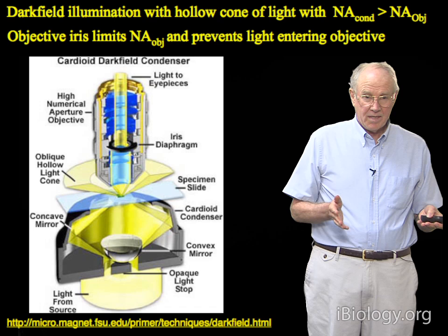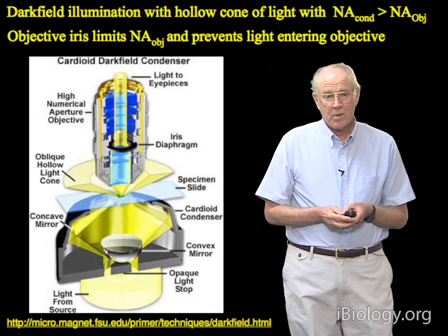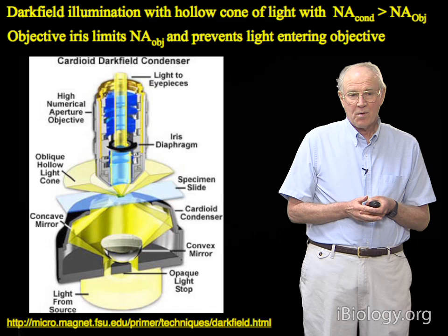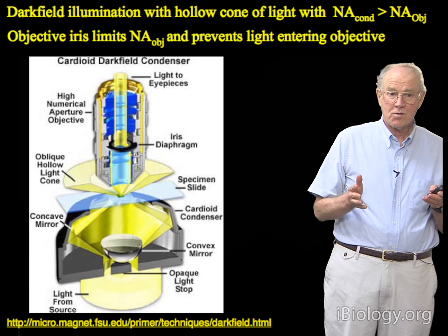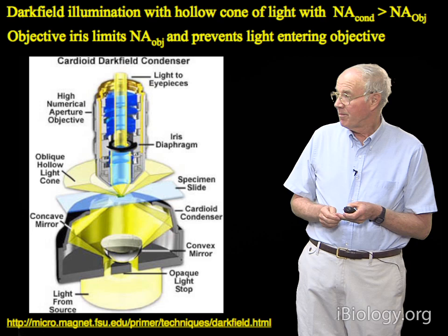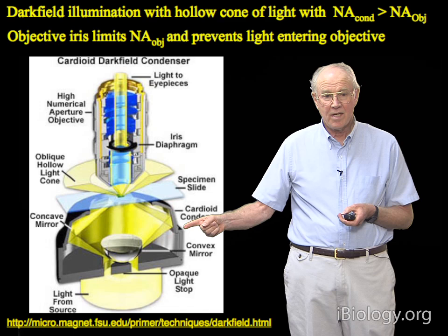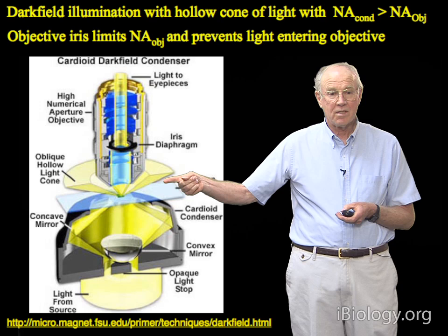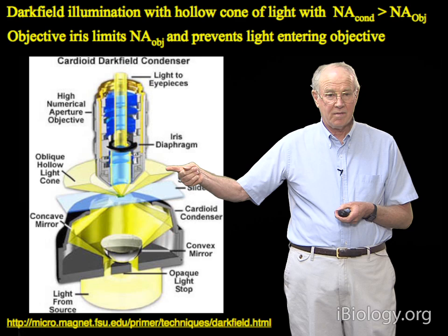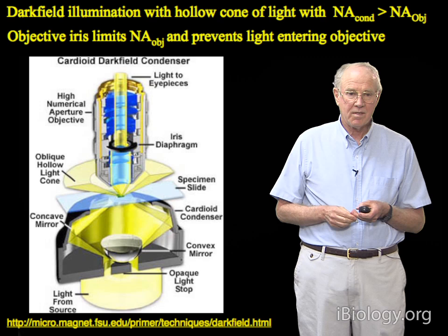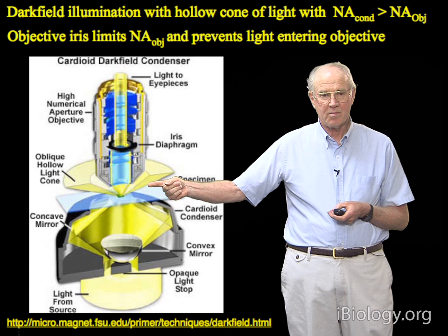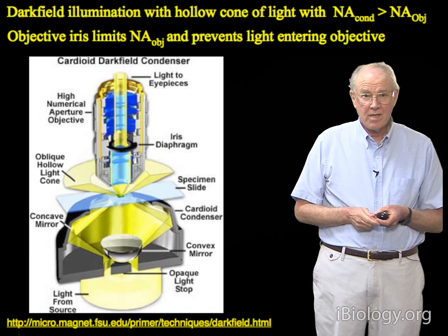Dark field as a microscopy technique is not done the way Zernike did in his experiment. We want to have some resolution normally in dark field microscopy. The principle is the same, but one uses condensers that have an annulus of illumination whose numerical aperture — the refractive index in the specimen times the sine of the angle of illumination — exceeds the objective's acceptance. Special condensers are used to generate this high angular illumination. The angle of illumination produces a hollow cone of light that's not capable of being accepted by the objective numerical aperture, creating a dark field, and then the scattered light generated by this illumination is collected by the objective and focused as spots in the image plane.